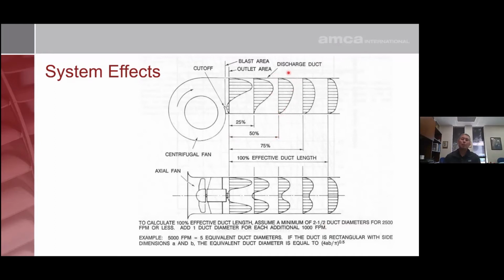So having some ductwork is better than having no ductwork. If you have some space constraints and don't have room for 100% of your effective duct length, if you can get 50% of it on there or something, you will get a substantial amount of regain back. In fact, you'll get most of it during that first 50%. This last 50% is more of a polishing portion of it, and you'll get maybe 20% of your regain at that point. So it's good to have this amount at least as a minimum.